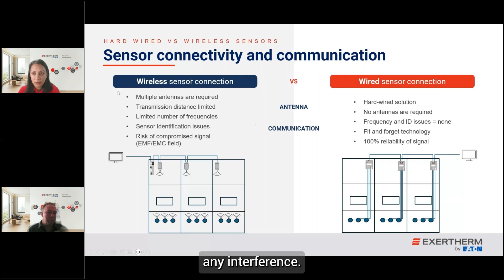Yes, you can protect, but as we all see in day-to-day life, wireless, RFID, any signal using some form of wireless communication is open to cybersecurity risk. And it's not just hacking into the sensor, it's hacking into the wider system and causing operational and security risks. Are you altering the value of a sensor? Are you telling someone there's an alarm when there isn't, so it's a false alarm? Or are you getting a non-alarm, where somebody's masking a signal?